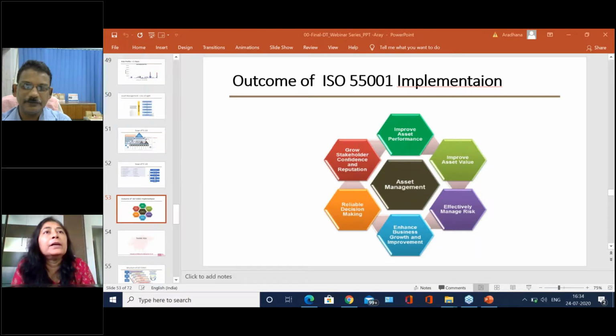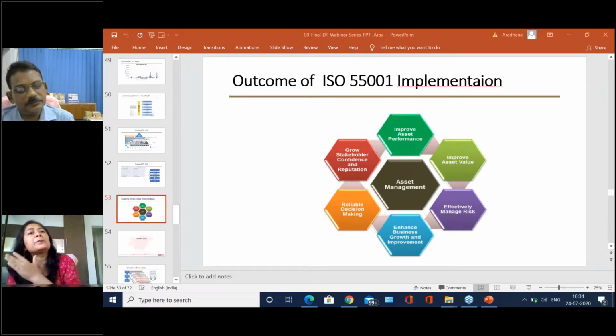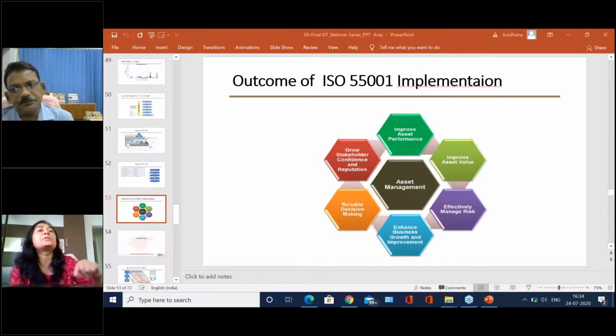If you're a utility, benchmarking matters. You're buying it, okay? So at least you should know what my benchmarking is, where my transformers are. If I bluntly go and measure it and it comes to 4%, I will not allow those transformers to be in the system for a long time. If it's below 1%, you're happy. At 2%, okay, I'll run it. So it's benchmarking - you have to trust the value, and that is what matters.